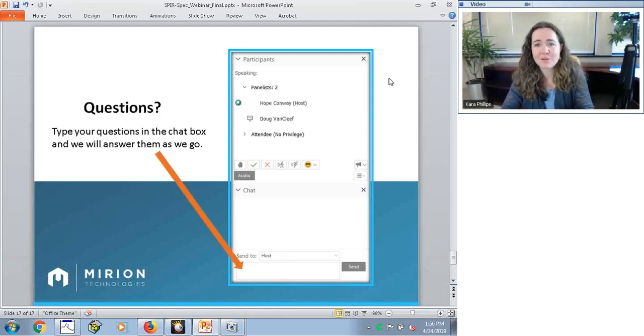Another question we have here is how long will the device operate on a full charge? There's a few different things that depends on. We mentioned earlier that it does operate in a low power mode. That means that the device display will be turned down until an alarm occurs, and that's going to have a slightly longer battery life, as long as 11 hours. If you are operating it more constantly and continually using it for operation, it is about 4.5 or 5 hours that we expect to see. So depending on the level of activity, 4.5 to 11 hours. Good question.